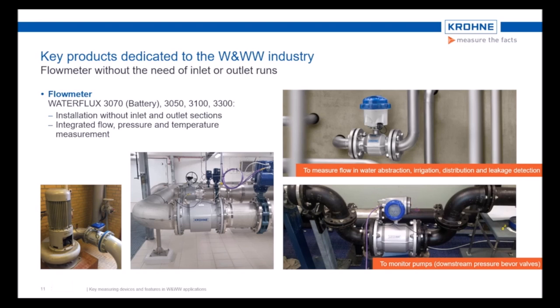So an integrated pressure sensor within the flow meter, which is also required to measure the flow, is therefore interesting to at least cover one of the required pressure sensors. An external analog one before the valve can, for example, be powered by a battery-operated GSM module, which is also transmitting all the signals to a remote control room. The temperature sensor will often be used for monitoring to prevent the growth of bacteria like Legionella, which can occur when a certain drinking water temperature has been exceeded.